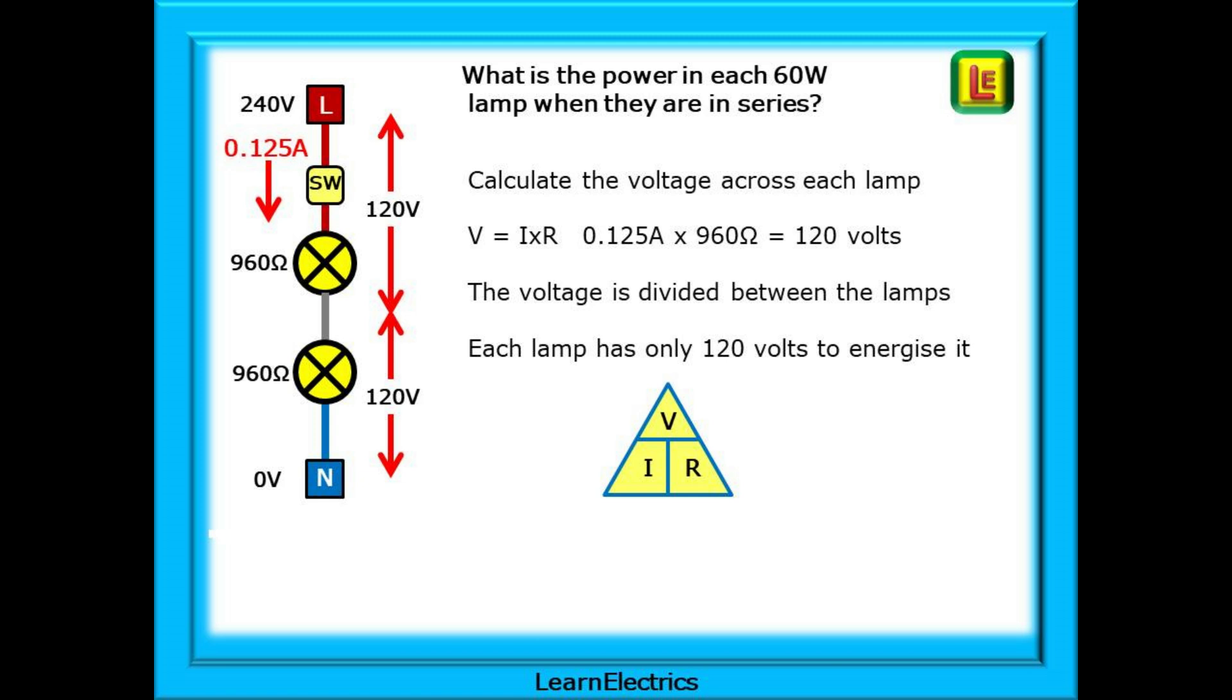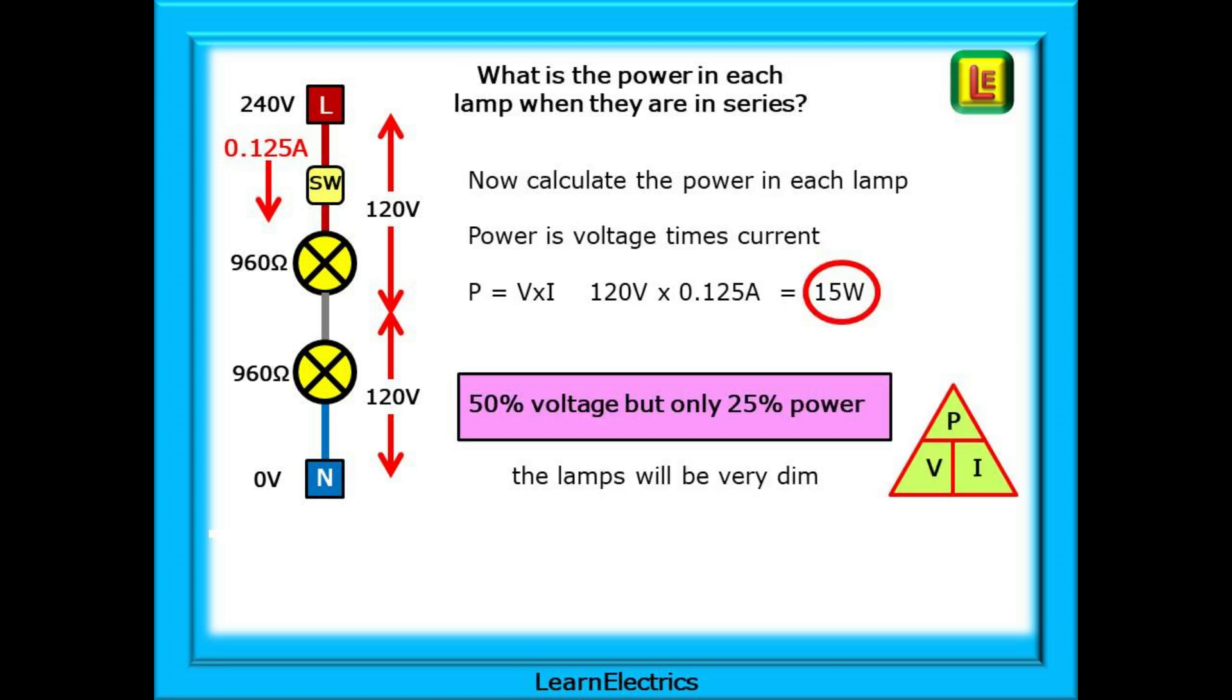This means that each lamp has only 120 volts to energize it. Next, calculate the power in each lamp. Power is voltage times current. So we have P equals V times I, which is 120 volts multiplied by 0.125 amps to give 15 watts of power for each lamp. So we have just 50% of the voltage but only 25% of the power. The voltage has dropped by half but the power has dropped by a half of a half. The result, very dim lights. And this is what you will see as you walk into a room where the lamps have been incorrectly wired in series.